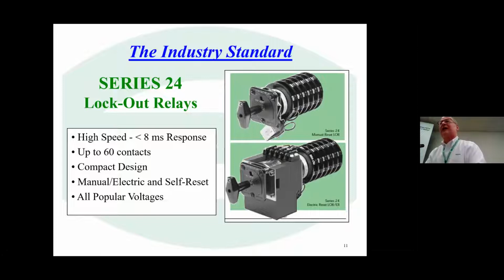an emergency lockout switch that says if I've got a problem on a substation and a transformer, let's say, I want that protective relay in the substation to trip a lockout relay and disable any possible control circuit that's going into that transformer control scheme to prohibit it from energizing if there's a fault in the transformer.